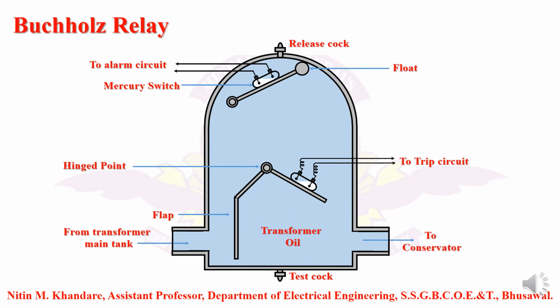Now we will see the operation of it. If an incipient fault occurs inside the main transformer, the incipient faults are nothing but the slowly acting faults which can't be identified easily, but they will be recognized when a large damage has occurred. So for protecting the transformer from the incipient faults we are using this system. Now whenever an incipient fault occurs inside the transformer tank, obviously it increases the temperature of the transformer oil. Due to that the evaporation of the oil takes place, and that's why hydrogen gas can be evolved.